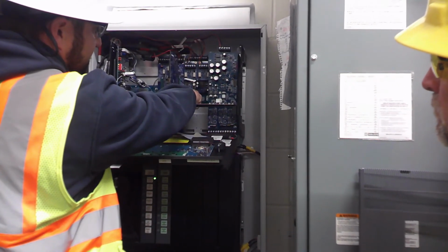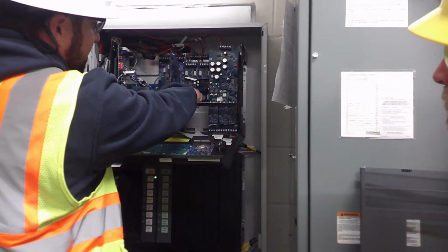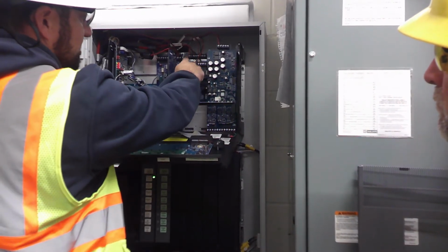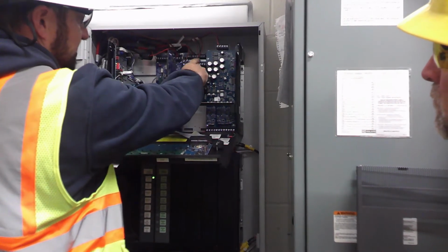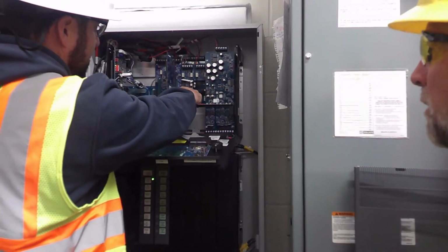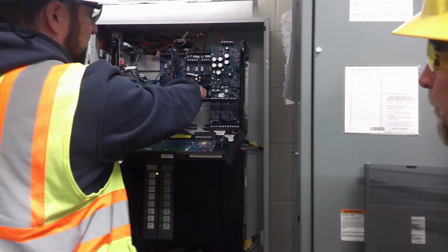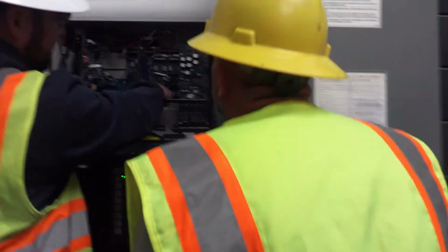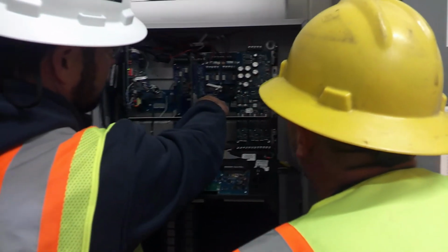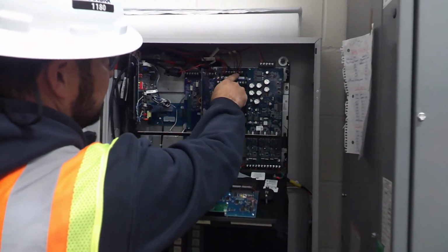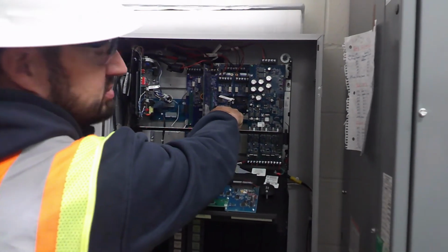So if there's an earth fault, negative or positive, it doesn't specify on the earth faults what loops they are. It will just tell you something on this card has an earth fault, either positive or negative. Process of elimination. But the loops, if you see over here where it says loop A, B, C, and D, if any of those are lit, that designates A, B, C, or D. That is an isolator loop light.